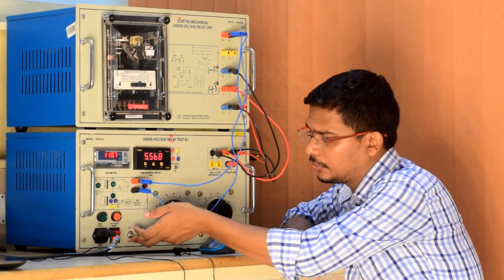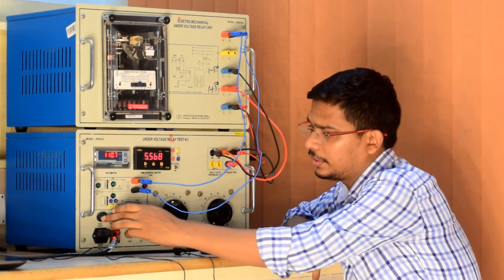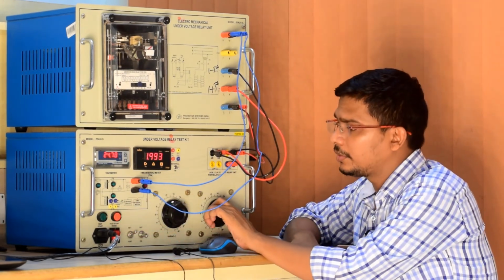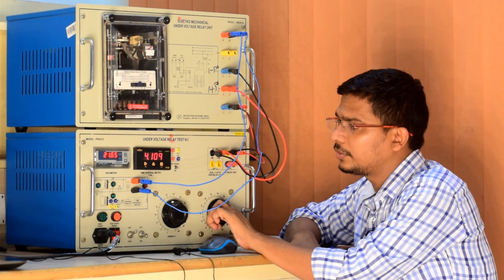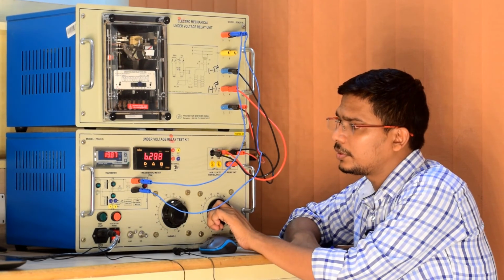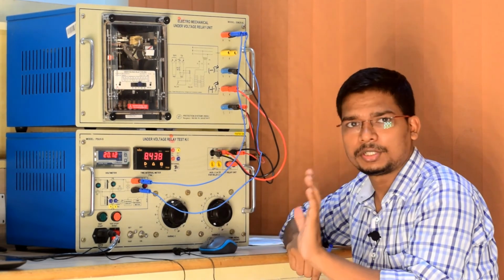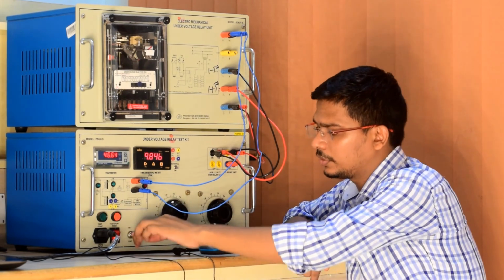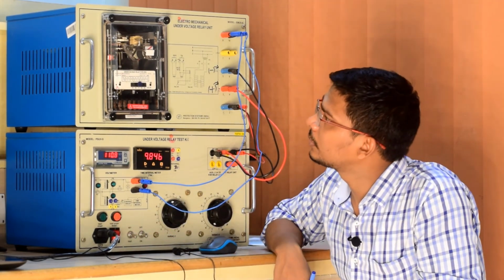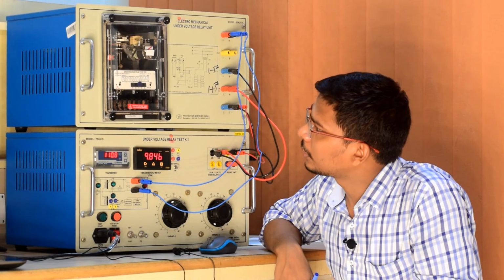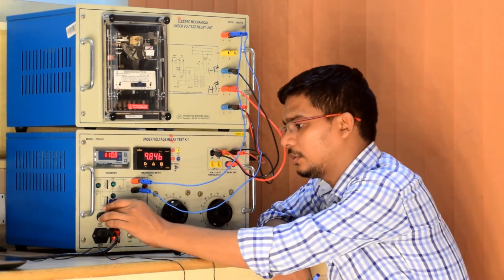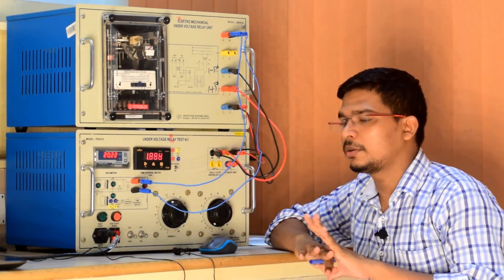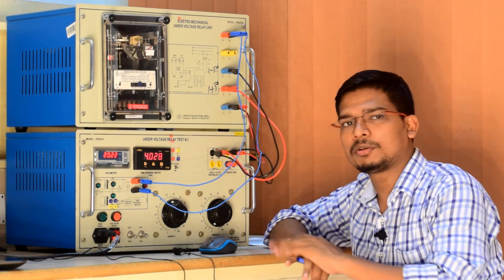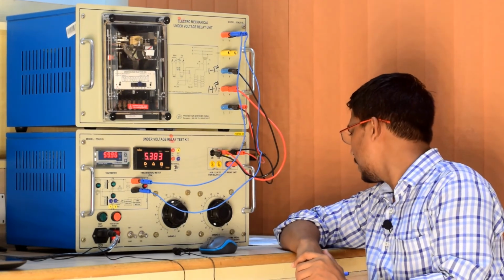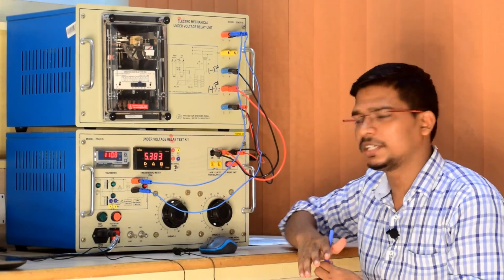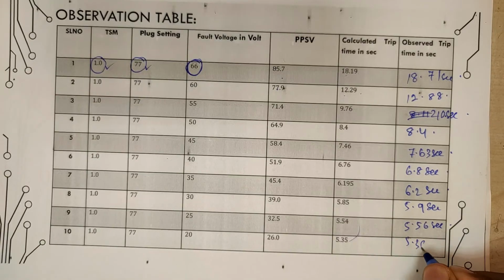Our last observation is 20 volt. Turn off, put to set mode, then turn on the circuit breaker, and reduce the voltage to 20 volt. Okay, a little more. Okay, 20 volt. Turn off, test mode, wait, so that the relay comes to its normal operating mode. It came. So test, start. We are applying our last observation, 20 volt, and our expectation time is 5.35 seconds. We got 5.38 seconds.